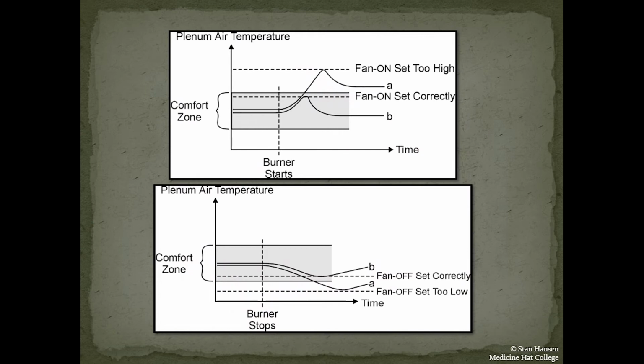When setting up the fan control, we need to consider economy, comfort, and proper cycling. We set up two different set points. The high set point turns the fan on and should be set just inside the upper comfort level. The low set point turns the fan off and should also be set just inside the lower comfort level. If the fan set points are set either too high or too low, what will occur is either the room is going to get too warm or too cold.